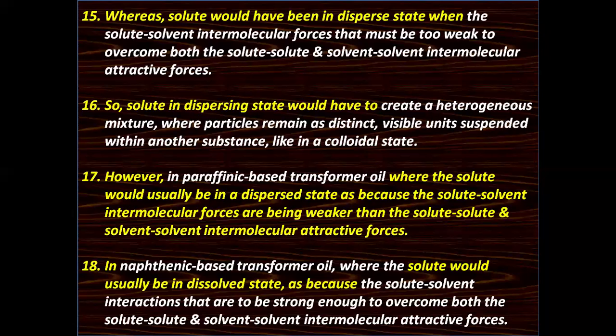However, in paraffinic based transformer oil, the solute would usually be in dispersed state, because the solute solvent intermolecular forces are weaker than the solute and solvent intermolecular attractive forces. In naphthenic based transformer oil, the solute would usually be in dissolved state, because the solute solvent interactions are strong enough to overcome both the solute and solvent intermolecular attractive forces.